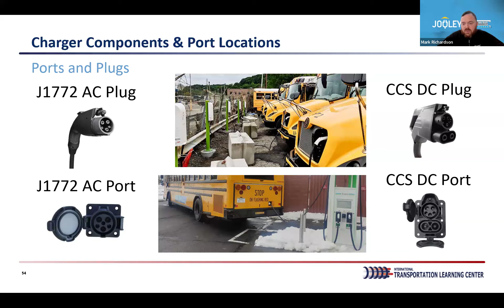Number one, and in my opinion the most important, is to initially inspect the charge head for cleanliness and damage. You don't know who previously handled that charge port - they could have dropped it, or gotten mud or debris inside the charge head. So you do not want to plug that charge head into the bus, because you'd essentially be cramming debris inside the charge port, which would not be good. Also check for damage - if it was dropped, it could have cracked or a piece could be missing. Ensure your charger and charge head are always in good operating condition and free of debris.